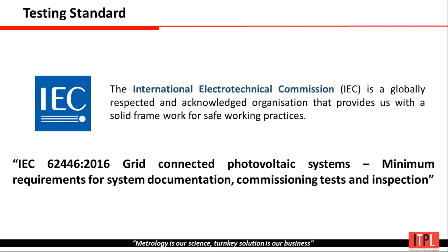So before going for testing of a solar power plant, we have to make sure that the safety aspects are okay. For the safety aspect, we can measure a few parameters like earth continuity. You can check the earth continuity value between your solar panel and your earth pit, and it has to be always on the lower side. It will always be in the range of 0.02 ohm, 0.03 ohm, 0.05 or 0.01. So earth continuity is the first point.